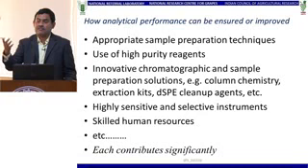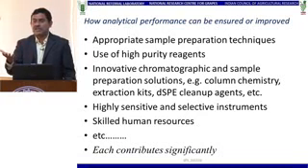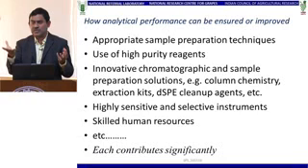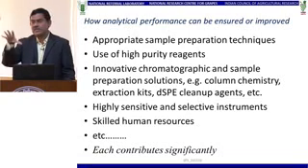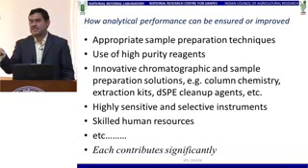Otherwise, your friends from various LCMS, GCMS instrument manufacturers will not be useful to you, because the solvent will produce so much residue that will be deposited in your ion source, on the curtain plate, on the cone, everywhere, and that will reduce your signal intensity substantially. And probably every alternate day you have to clean the machine, otherwise you will not get sufficient sensitivity.